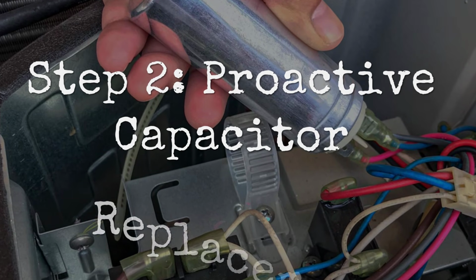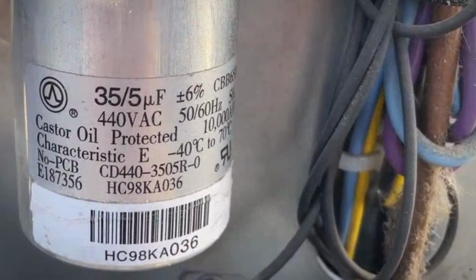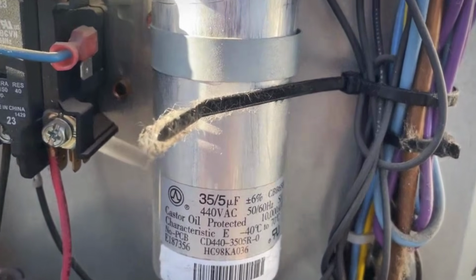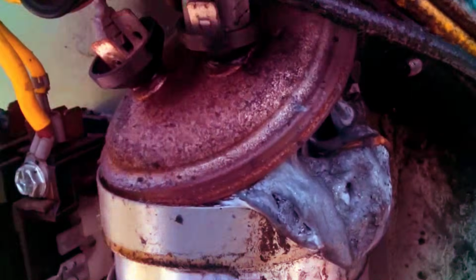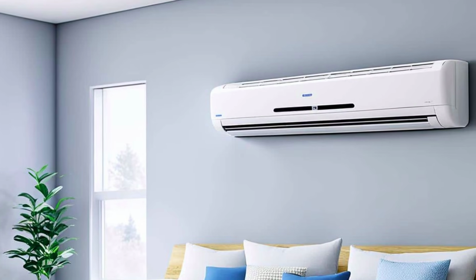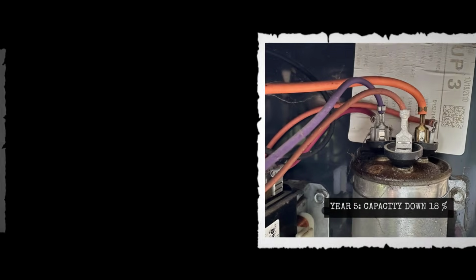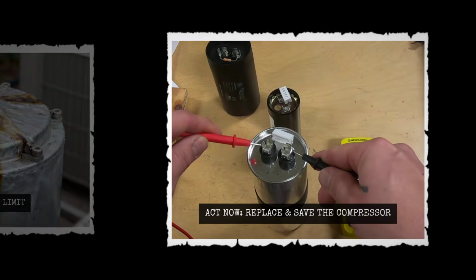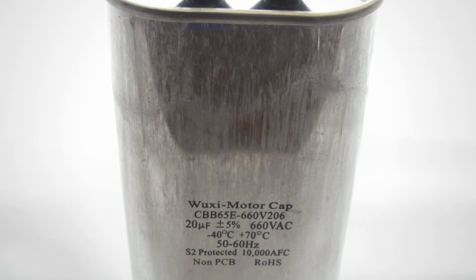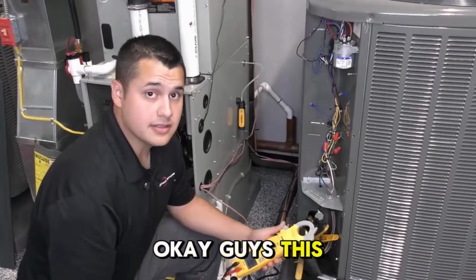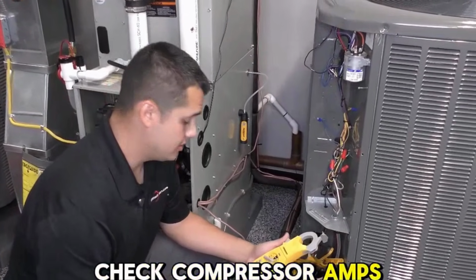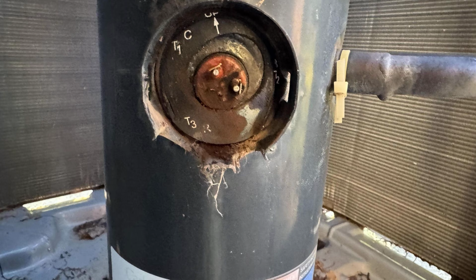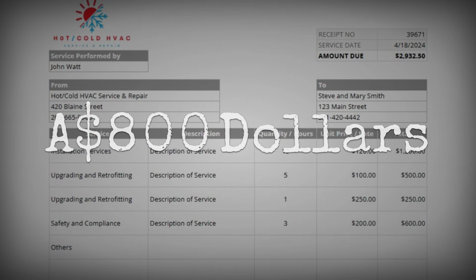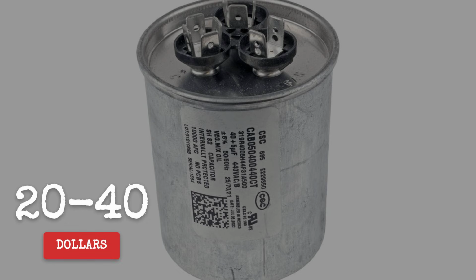Step 2, proactive capacitor replacement. The run capacitor, the component that keeps the compressor motor running after startup, degrades predictably with heat exposure. In a budget tier unit running through Australian summers, the capacitor typically reaches the end of its useful life between year 5 and year 7. A capacitor does not always fail dramatically. It often just degrades, causing the compressor to work harder on each startup cycle, accelerating wear and eventually producing the catastrophic failure that a technician will quote you $800 to repair. A quality replacement capacitor costs between $20 and $40 in parts.